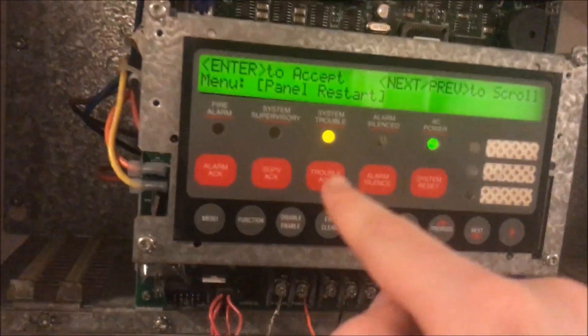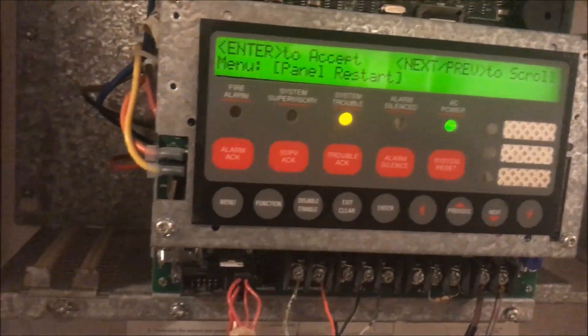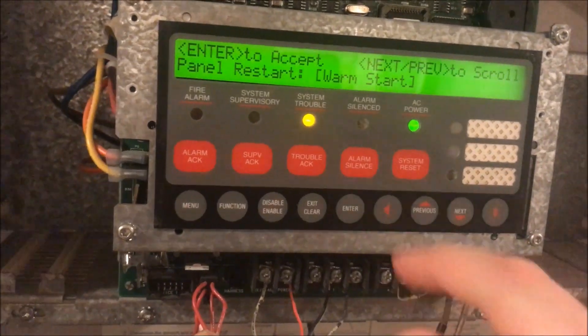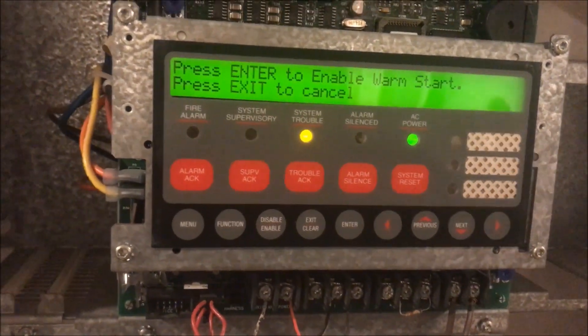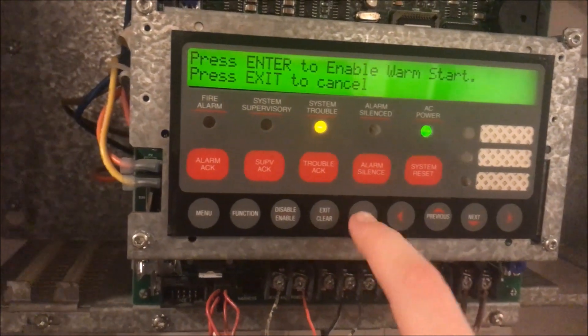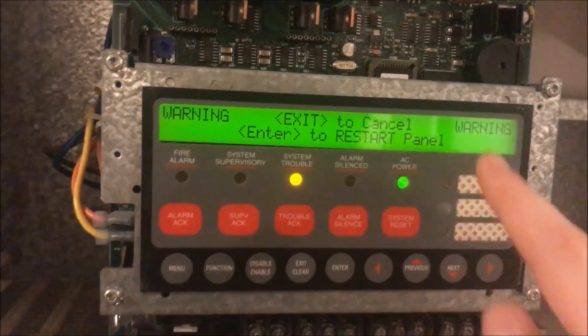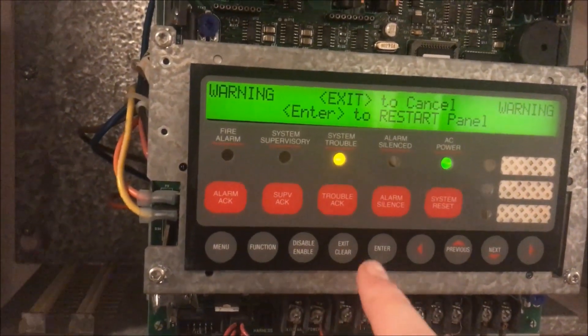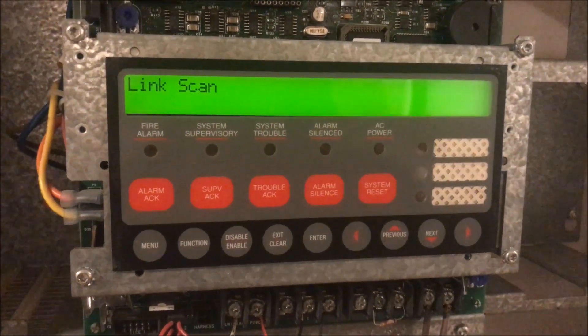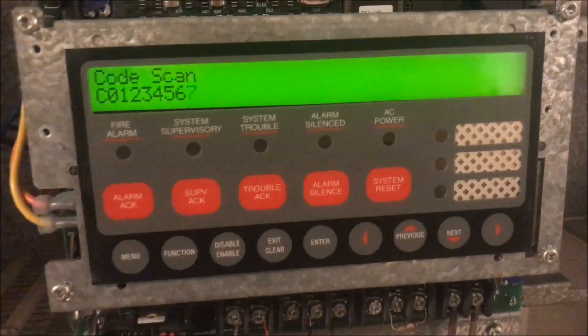I'm going to do a panel restart now, because this service mode trouble won't go away just by logging out — at least not on mine. We're going to do a warm start, which keeps the date and time but restarts the computer. It gives you a warning: 'You are about to restart the panel' — and we say yes. The panel is now booting up.